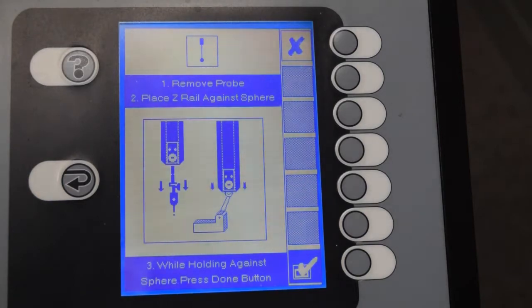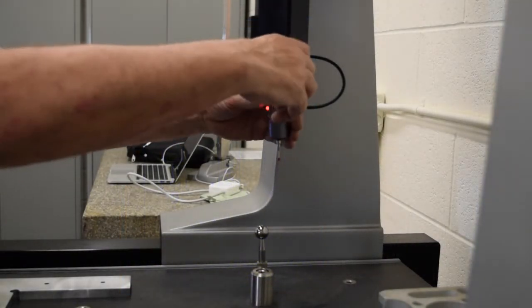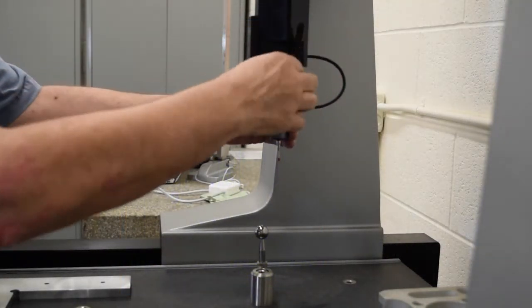Once the origin has been set, the next thing we need to do is calibrate the probe, and the first thing we do here is we select probe type, which is TTP, or touch trigger probe.